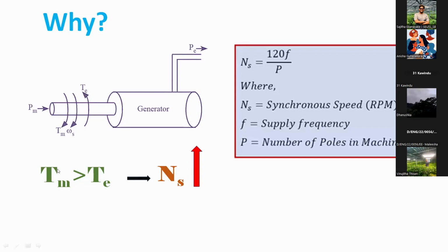The first thing that happens is that demand and supply are not balanced, meaning mechanical torque is greater than electrical torque, then the speed of the rotor increases, then the frequency will be increased. The other way, if the mechanical torque is less than the electrical torque, the rotor will decelerate, meaning frequency will drop. That is why we have to always balance the supply and demand.